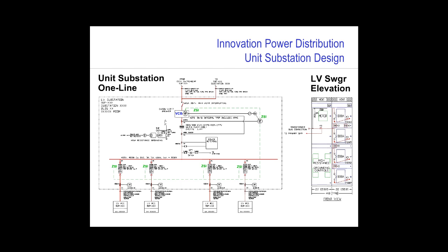On the right of this slide, I'm showing the low voltage switchgear elevation that corresponds with the one line at the left. I slipped one extra thing in here on you. As you can see, I have some room in the first vertical section at the bottom to install a high resistance grounding system. This HRG system installs a resistance between the neutral and ground connection on my low voltage power distribution, allowing me to reduce the opportunity for an incident of a line to ground fault. Beyond the scope of today's discussion, but in my view, again, an excellent safety feature that should be considered for future designs.